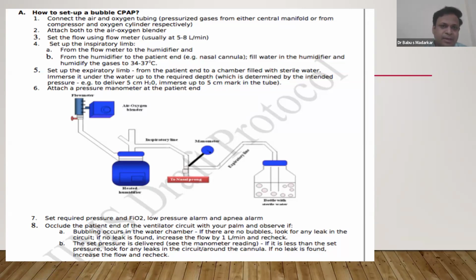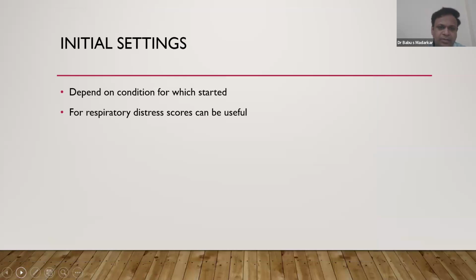Bubble CPAP is connected by the tubings, as we discussed here. We take the humidification chamber first, then make sure that we attach the inspiratory line to this, and there is one more line which goes to the interface through the nasal prongs. It goes to the baby. The expiratory limb is dipped into a sufficient amount of water, and there are markings here. We have to make sure that the humidity of the gases is well maintained by keeping the temperature at around 34 to 37. The expiratory limb is marked at a certain number, and that is centimeters of water. And there has to be FiO2, which has to be set. So this is the basic outline of CPAP settings.